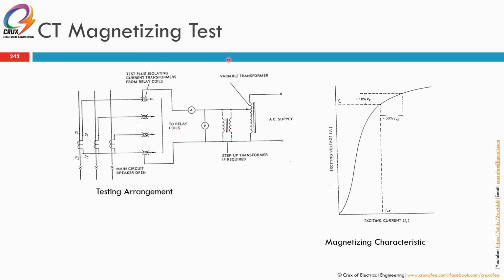Third is the CT magnetizing test, or what we call the knee point curve test. This CT magnetizing test can be done on all types of CTs, whether it's a metering CT, protection CT, or the class PX or class X CTs. The testing arrangement will be, you will be injecting voltage across the CT secondary. Then one of the meters will be measuring the excitation current to the CT. Then you will plot excitation voltage versus the excitation current.